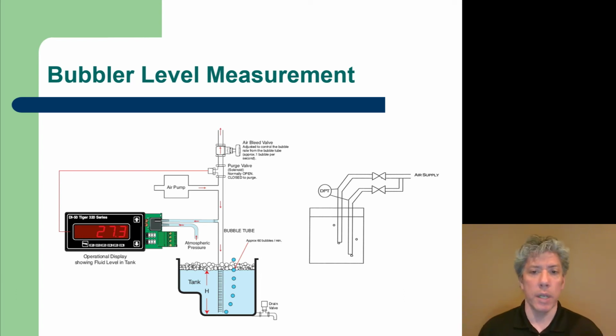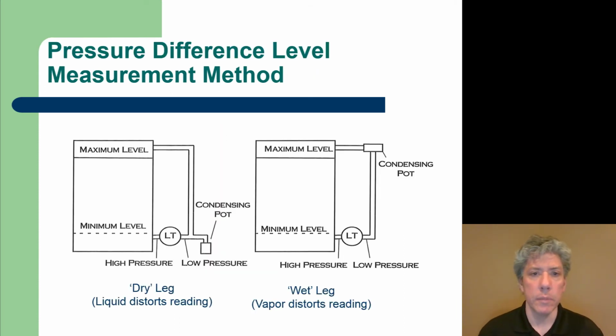If what you want is to compensate for density, because density can make a big difference and throw your height readings off, because understand you're back calculating your height readings from a pressure, well then this is a way to get a measure of density in addition to a measure of pressure difference for more accurate calculations of height. There are other methods for measuring pressure differences. You'll see on the left a dry leg, and on the right hand side a wet leg measuring scheme.